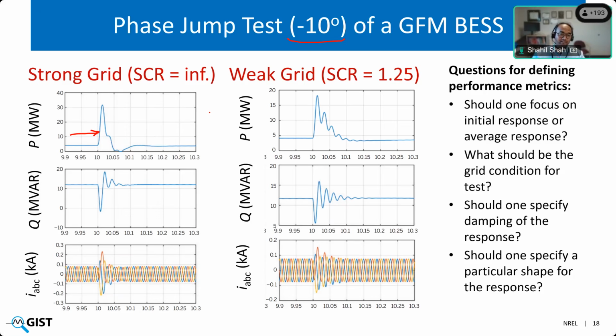On the left side, the response is done when there is no impedance between the grid forming resource and the ideal voltage source used for emulating that phase jump. That means the SCR is infinite. On the right is when we insert impedance between the ideal voltage source and the grid forming resource to create a weak grid condition of SCR of 1.25. Here the response is similar but smaller. As you can see, the response jumps by around 15 megawatts compared to 25 in the previous case, and the response is also more oscillatory.